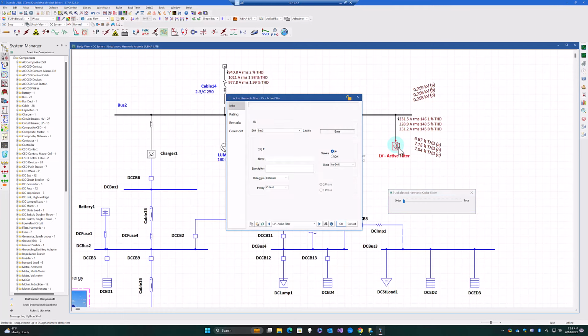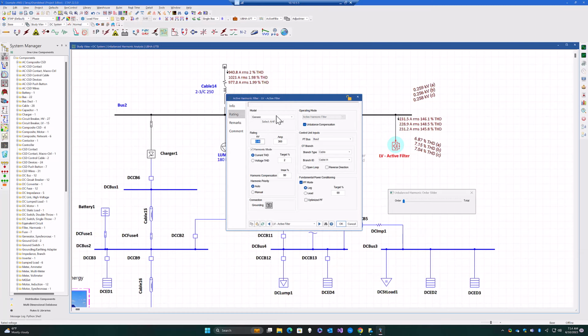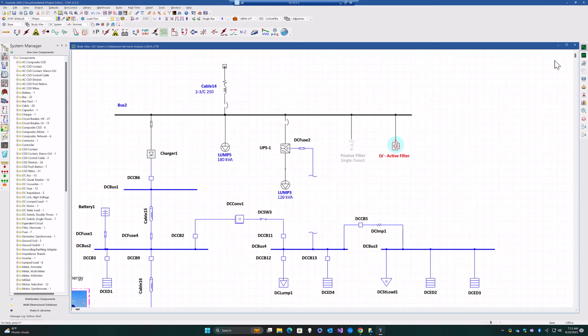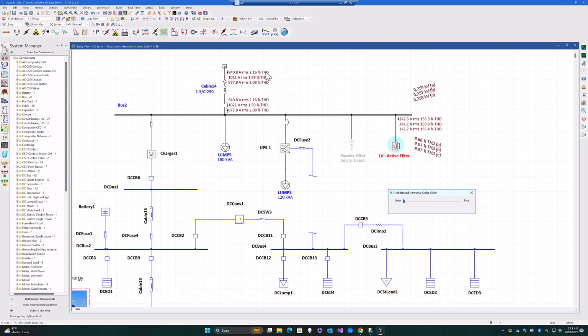The active filter in this case happens to be a generic active filter, but you also have the ability to choose a Schneider Electric PCS-N, which has a neutral wire or 4-wire system, or a PCS Plus. Using these filters, you can also achieve the simulation itself. We use the proprietary logic that has been provided to us by the vendor to give you the exact response and output from that particular harmonic filter. Now, this is the steady state response of the active filter. There is a bit of a settling time that's usually involved as the active filter is engaged and it starts measuring, sensing, comparing, and then it starts injecting. So there is also a time domain feature of the active filter that we are also able to simulate inside ETAP.